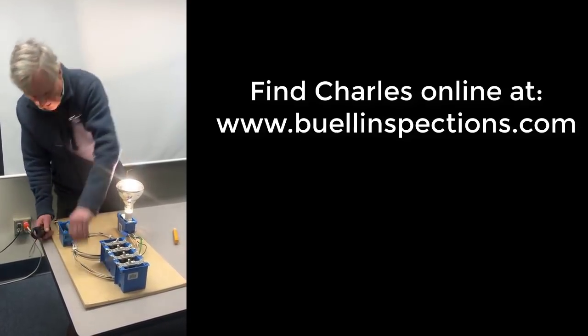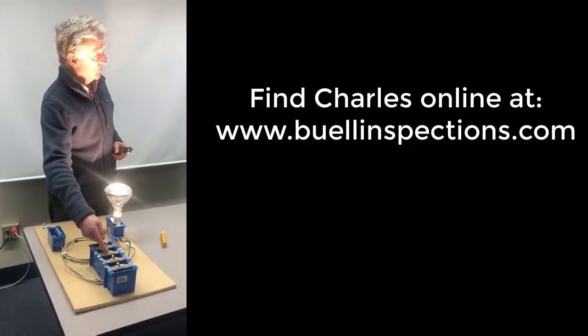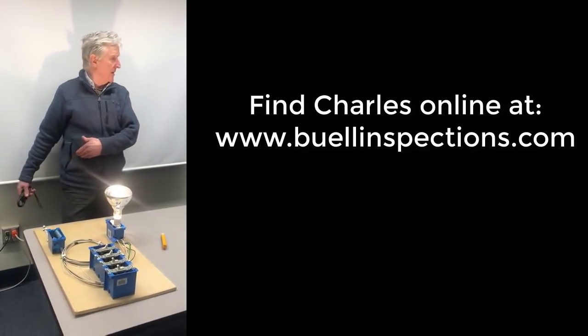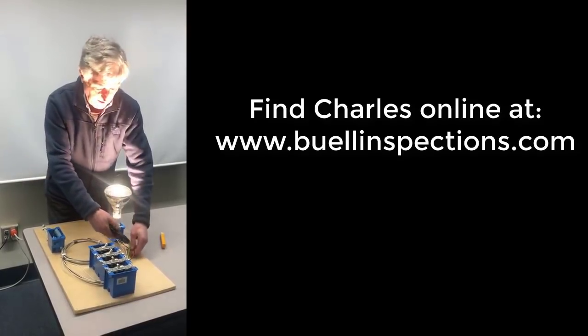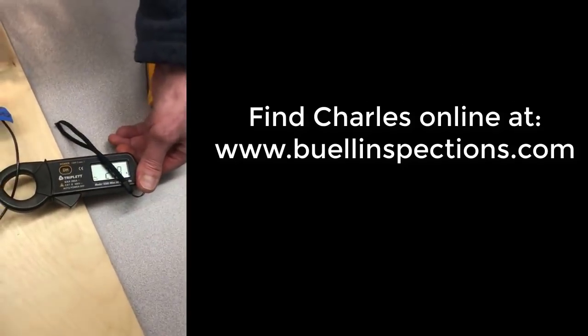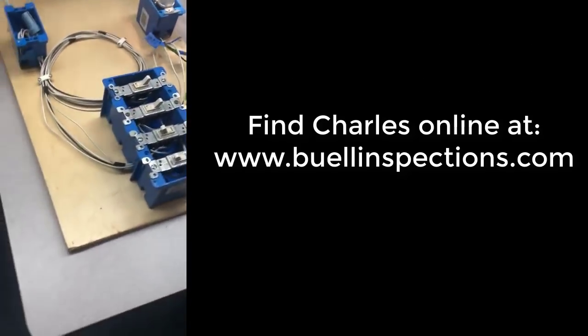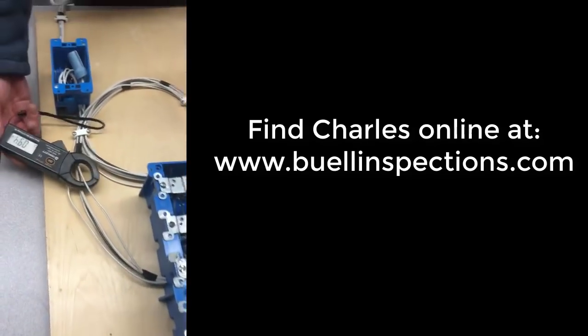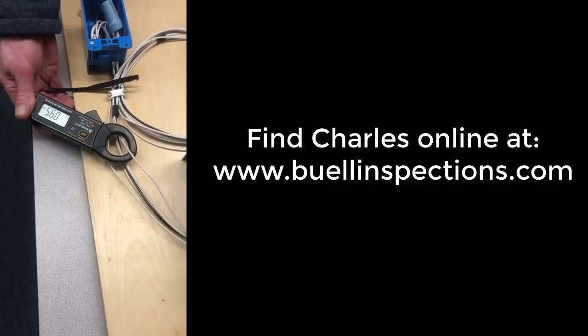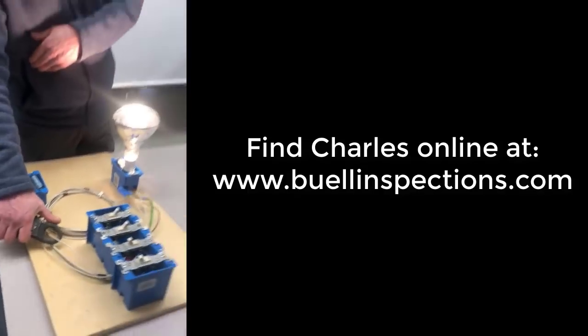So now I'll turn on the other 14 gauge wire. So now I have 2 paths back to the transformer for that current to flow on. You'll see we still have 2 amps on the 14 gauge hot side. And look what happens when we pick up one of the 14s. See, we have half of it now. So half the current's flowing on one of the neutrals, half the current's flowing on the other neutral. Parallel paths, 2 ways back.